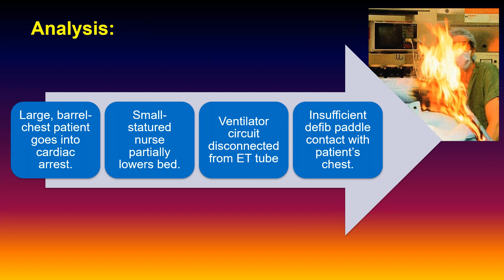And ultimately, what we were able to put together is that this patient was a big barrel-chested guy, and they were in cardiac arrest. This nurse was relatively short in stature, nothing wrong with that, but they typically will lower the bed to facilitate chest compressions. Well, the bed didn't go down. They didn't lower the bed very far, and the patient had a trach tube in, 100% FiO2 with 100% oxygen. The nurse, being relatively small in stature, with a big patient and the bed relatively high, wasn't able to make good paddle contact with the patient. And here's where the arc occurred. We even had a picture of the paddle that showed charring on the paddle and supported that.